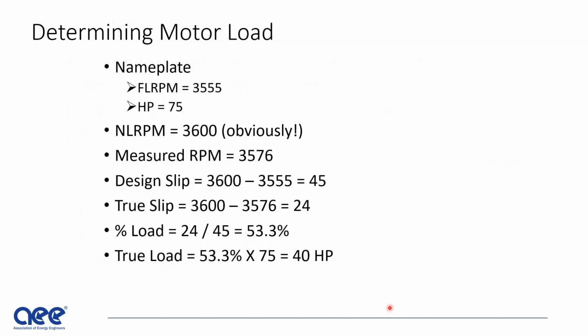So if we do a quick example here, we have a full load RPM of 3555. So right there, you know that the synchronous RPM is 3,600. There's no other choice. The horsepower is 75. We go through the simple math, and you can see that we are 53.3% loaded, which means that 75 horsepower is running at 40 horsepower.